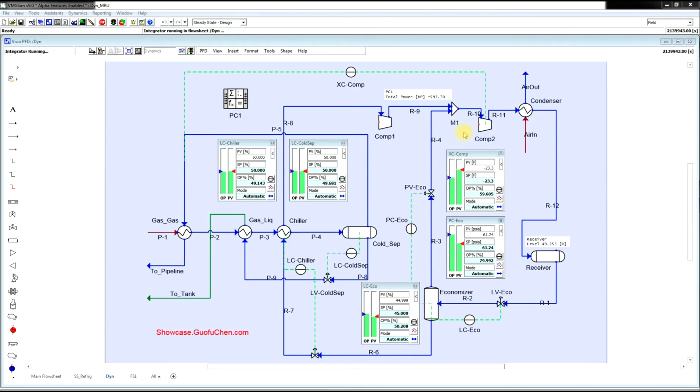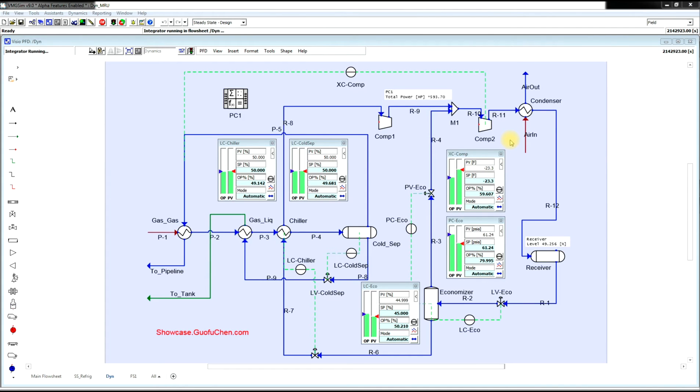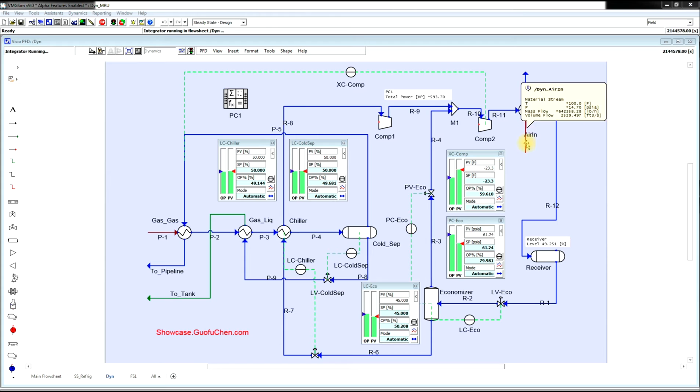Since we have a compressor, do you think we need to control the compressor discharge pressure? No, the compressor discharge pressure is actually determined by the condenser and the air temperature.